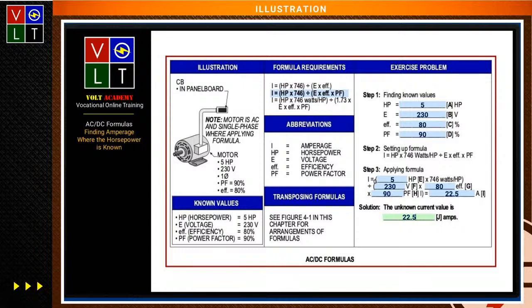So this formula here, you're going to take the horsepower, multiply it by 746. So each horsepower is multiplied by 746, and you get that value. Then you're going to take the voltage, and looking at this, it's a single phase, so I don't have to put the 1.732 with this. So I'll just take 230 volts. Then I'll multiply that by the 80% efficiency, and then multiply by the 90% power factor. And then you take that value, divide it into your horsepower, and it's going to give you a value of 22.5 amps. Pretty simple. Right.